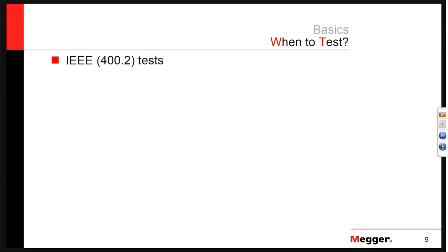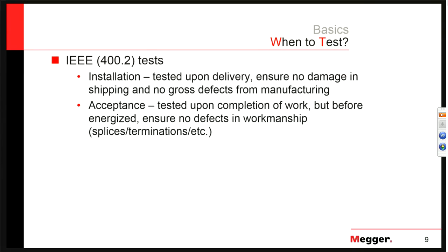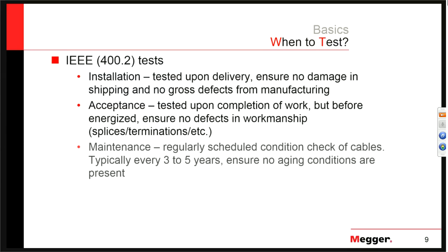When do we test? IEEE standard 400.2 lists three occasions. First is the installation test — basically a delivery test to ensure there's no damage from shipping. Second is the acceptance test — upon completion of work, when the cable is done but before we energize it. These fall under preventative maintenance, trying to pull out faults before energizing. Finally, there's the maintenance test schedule — a somewhat reduced voltage level, regularly scheduled check of the cables, typically every three to five years.